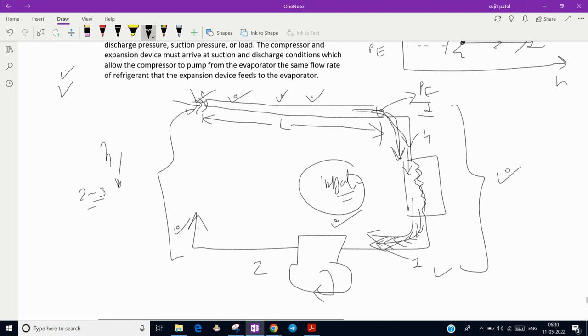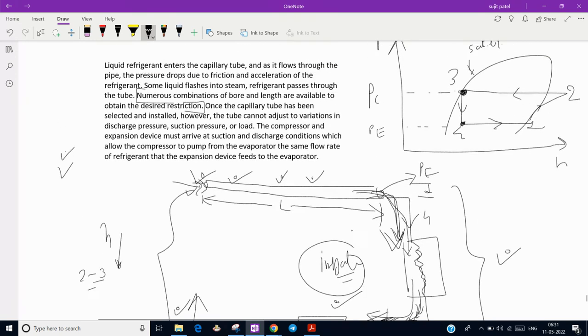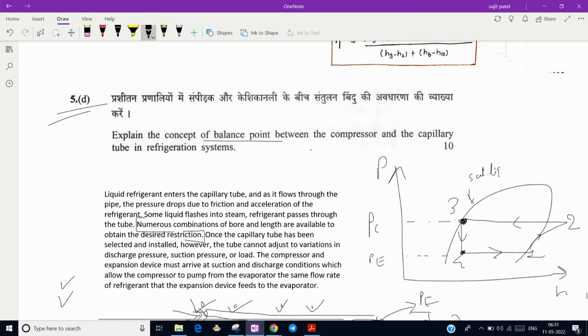When the exit pressure, suction and discharge pressure of both capillary and compressor is the same, and the same mass flow rate coming from the capillary tube is going to the evaporator and the same mass flow rate going to the compressor, this condition is called the balance point of compressor and capillary tube.